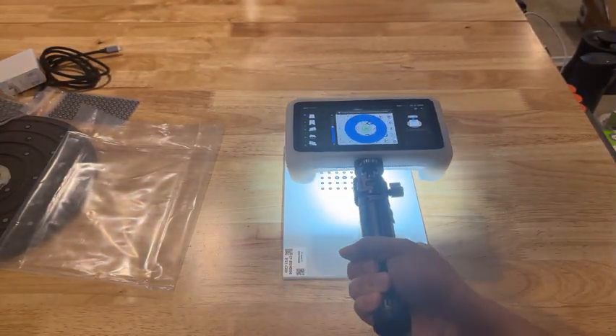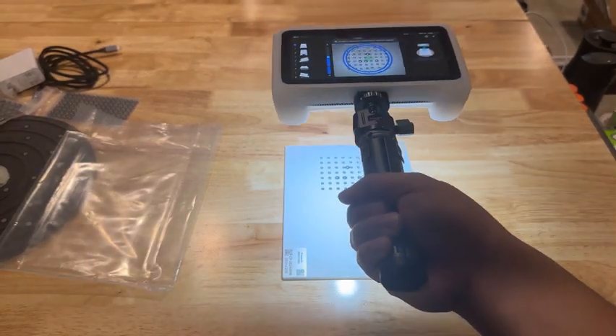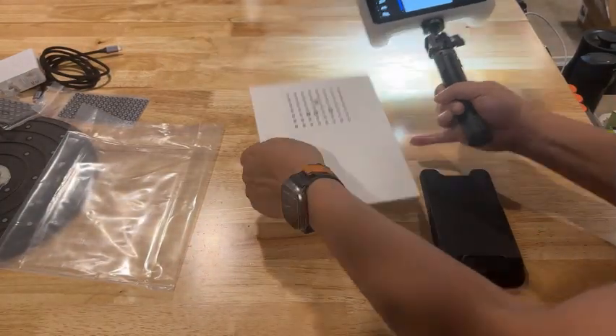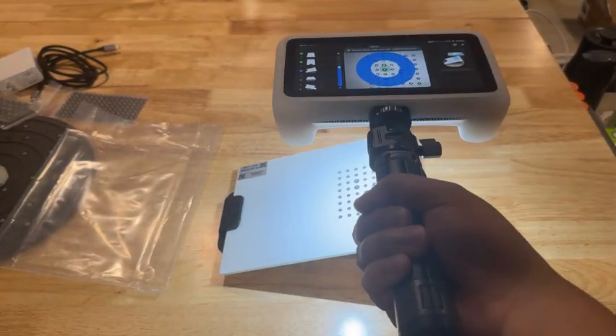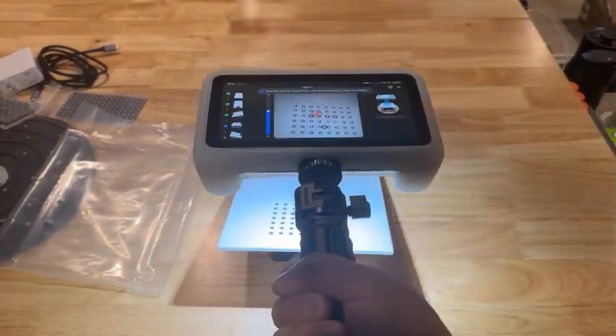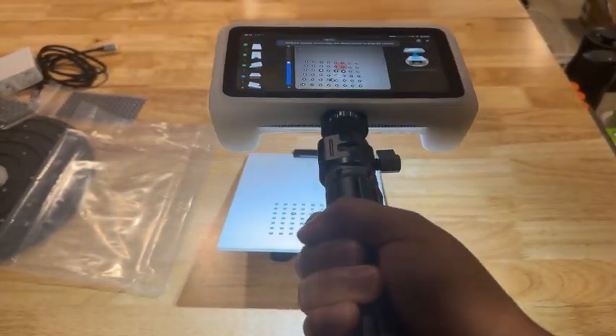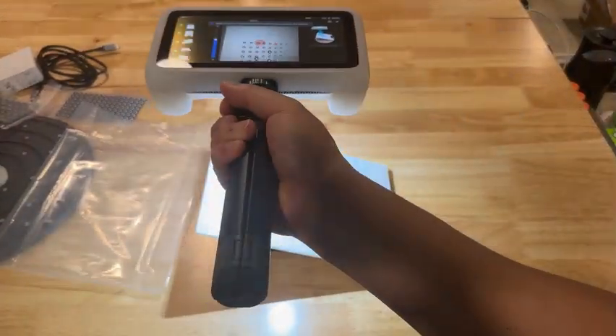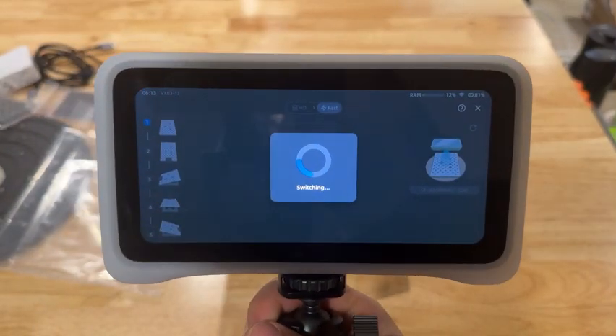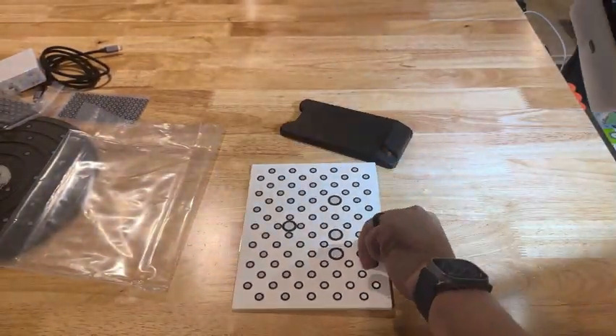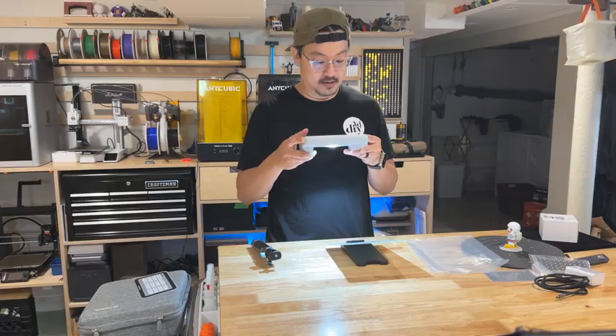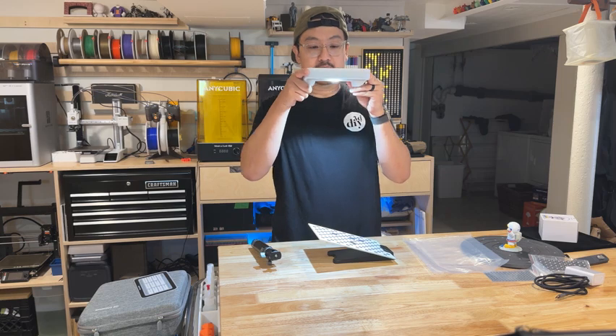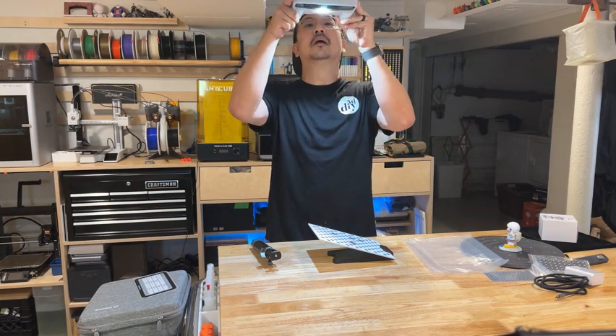The calibration starts with the HD cameras and using the calibration plate with the smaller dots, starting with calibrating the plate flat on the table, followed by positioning the plate on the stand at different angles. The calibration involves keeping the target centered in the blue circle on the screen, gradually and slowly lifting up till the blue circles disappear. It took some time getting used to keeping the scanner steady and not going too fast, but it's okay if you do, as you can always lower the scanner to capture what you had missed. Once the HD side is calibrated, you flip the calibration plate over to calibrate the fast scanning cameras. Calibration is suggested to be done every 7 days.